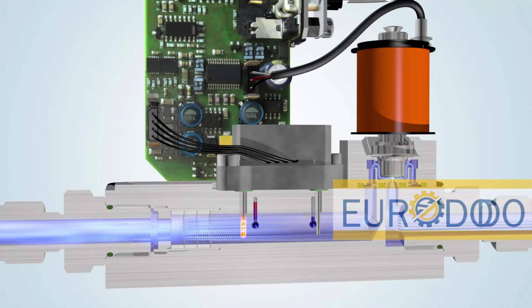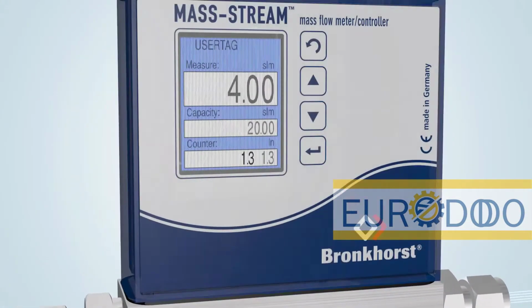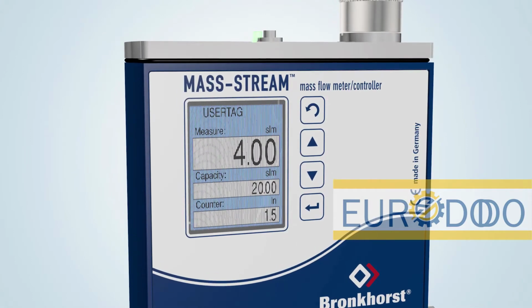One Mass Stream key element is the optional integrated multifunctional and multicolor display with operator buttons on the instrument. The modern-looking display has multiple functions, such as actual flow indication, totalization and alarms, and it is fully IP65 compliant.